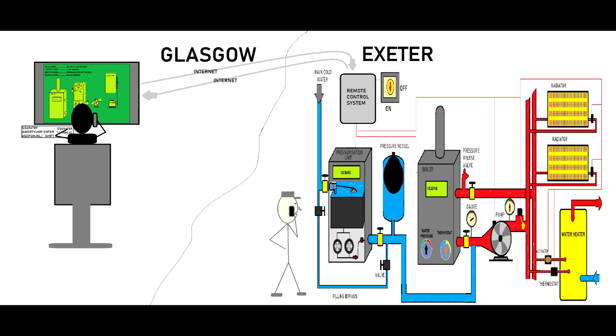Or the boiler is not running because it's got its own flow switch inside. And the programmable logic control is asking for the boiler to run. The client called you, you told him the boiler is running, nothing is wrong, and the client said it's very cold in the store because your integration doesn't let you know the fact that the boiler has a fault, and you only have a contactor status display on your HMI.